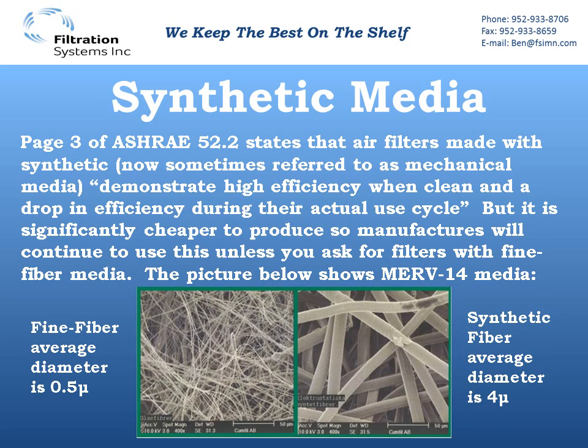Synthetic media is addressed in 52.2 in the 2012 revision right on page 3 of the standard. It states that filters made with synthetic media — some filter manufacturers are calling this mechanical media — demonstrate a high efficiency when clean and a drop in efficiency during their actual use cycle. It is significantly cheaper to produce synthetic media, so manufacturers will continue to do this because they can get a 52.2 report that makes the filter look really good. But in use, you have a struggle to maintain that efficiency and oftentimes it doesn't. So why buy a MERV 11, 13, or 14 filter if it's just going to drop down well below that anyway?